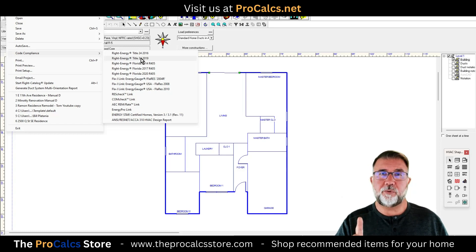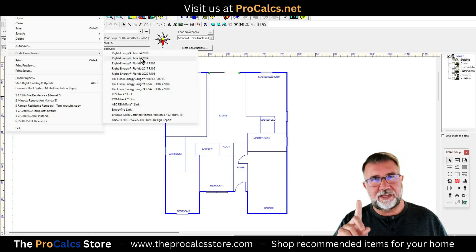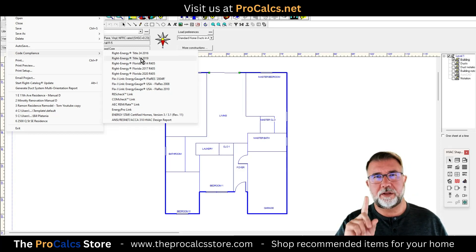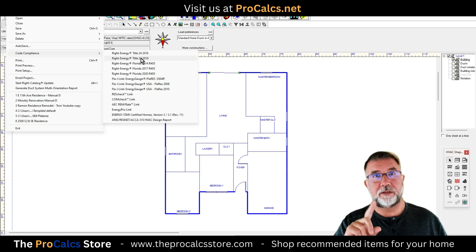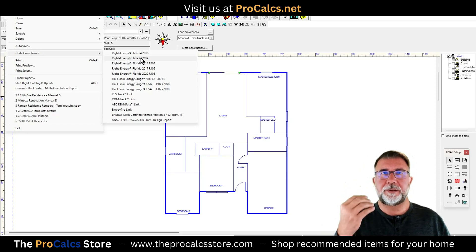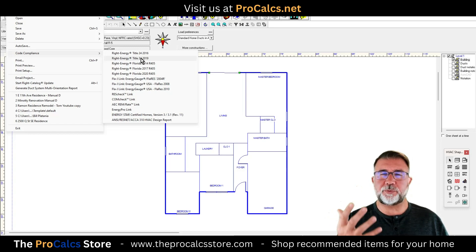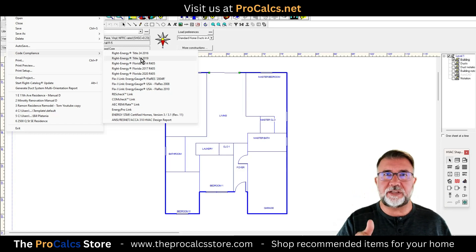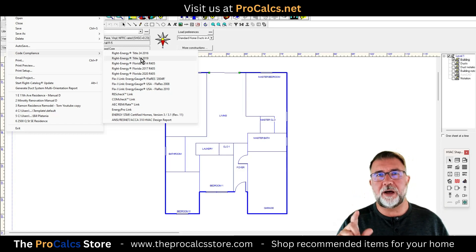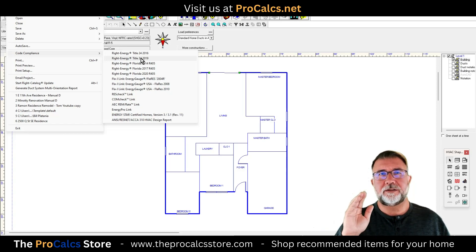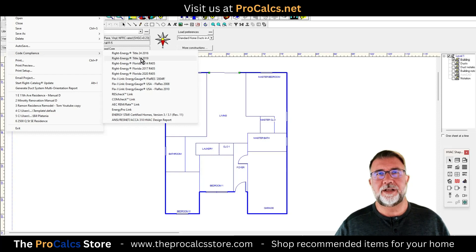It's very important to have the load calculations done first, then incorporate the energy calculations. The energy calcs must match the load calcs. If the volume's off, windows are different, or the AC tonnage, BTUs, SEER rating, or anything else doesn't match, you will fail at the building department — period. Whether they're both individually correct, if they don't match you fail. The building departments want to see the same equipment, same SEER rating, same size, same load calcs, same windows, same everything.